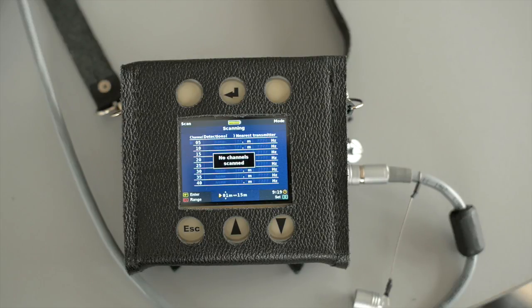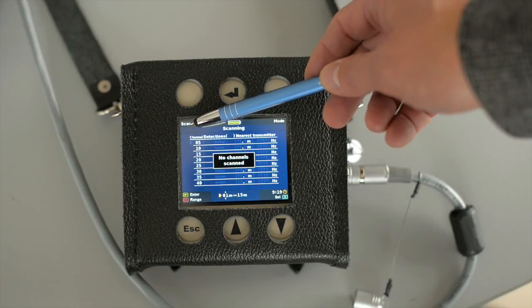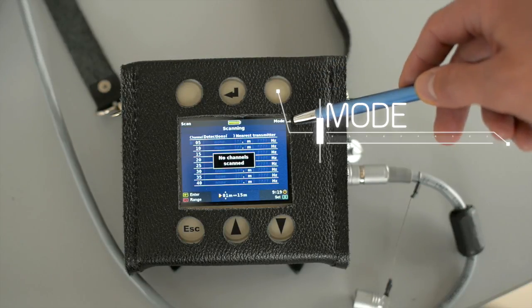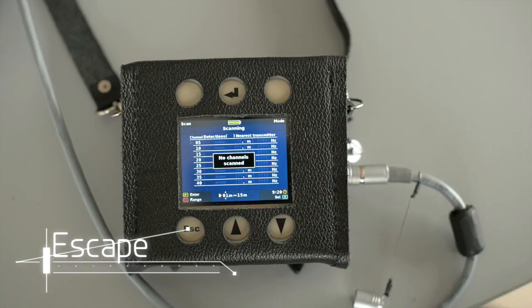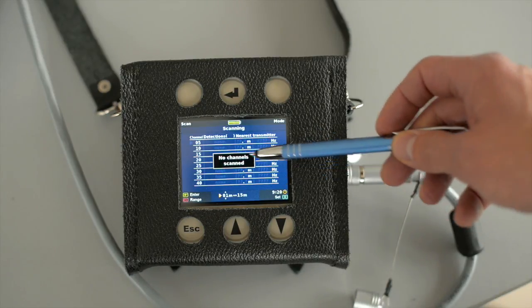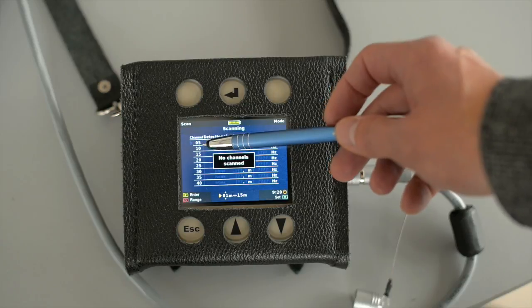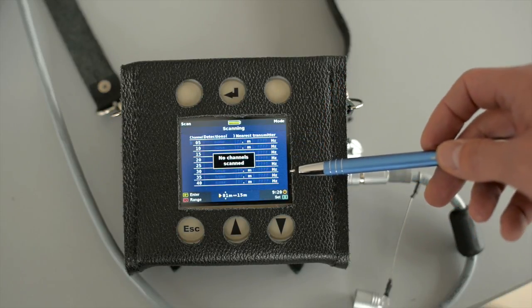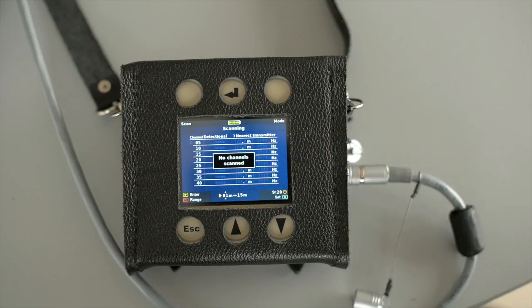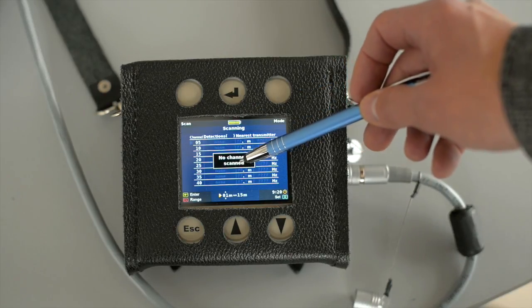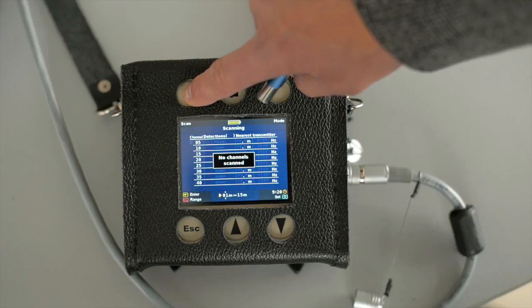The display shows functions for the various keys. By pressing a key, the relevant function will be performed. So, on the basic screen, we have the following function keys: scan key, enter key, mode key, arrow down key, arrow up key, and escape key. On this screen, we can see the table where each row represents one of 8 channels, from 5 up to 40 in increments of 5. In the center of the screen, we can see the window displaying information that the scan was not yet performed. To perform the scan, we need to press the key labeled Scan.